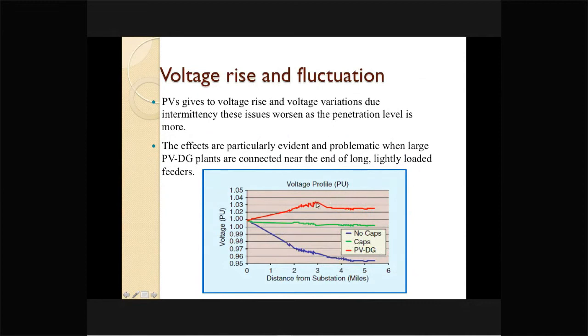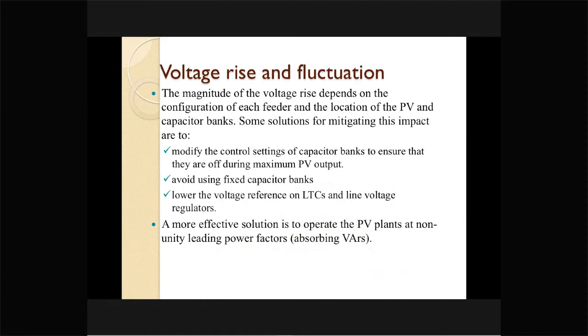However, after this point, if the houses do not have any photovoltaic on their rooftops, then the voltage remains more or less flat. So this says that the voltages at certain points on the distribution system, the node voltages, may see a voltage rise phenomenon, and that voltage rise may be coupled with voltage fluctuation when the photovoltaic power becomes intermittent, which could be due to cloud movement. To handle this voltage rise, generally we go for capacitor bank and OLTC operation, and OLTC operation, being mechanical in nature, creates a lot of problems in the grid-connected mode of operation.